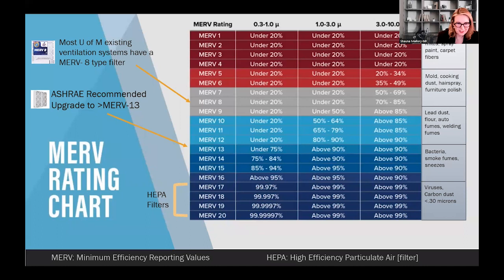MERV filters. I think more lay people have come to know what MERV stands for than ever before. For those of you who haven't heard it yet, it stands for minimum efficiency reporting value. And you've probably heard of HEPA filters, which are high efficiency particulate air filters. At the University of Manitoba, our existing building ventilation systems have a MERV 8 type filter in them. You can't really see from the little diagram on the left-hand side, but they're relatively thin. They're designed to get most mold, dust mites and pollens out of the air.